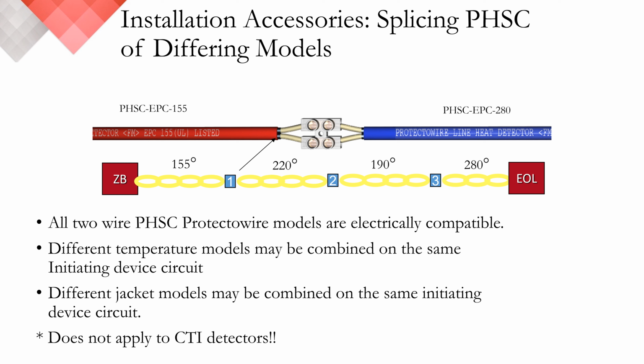Another benefit of working with standard digital linear heat is the fact that all our PHSC series detectors are electrically compatible. What this means is that it's possible to combine different temperature models on the same initiating device circuit. Since activation is predicated on the melting of the heat-sensitive polymers and exposing the conductors, we're only concerned about an on or off state. Combining varying initiation temperatures enables you to accommodate any fluctuations in ambient conditions you may be faced with without the need to zone a higher or lower initiation temperature separately. Again, this is specific to PHSC series only, as CTI requires the use of our CTM530 interface module to provide the false alarm discrimination. It's not possible to combine different temperature detectors along the same IDC.